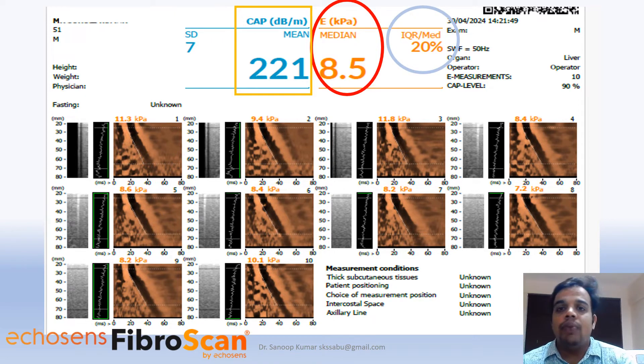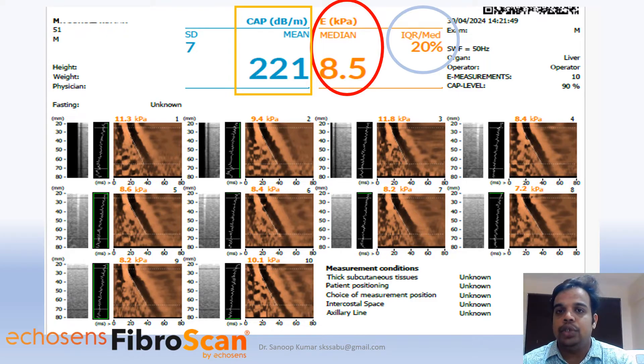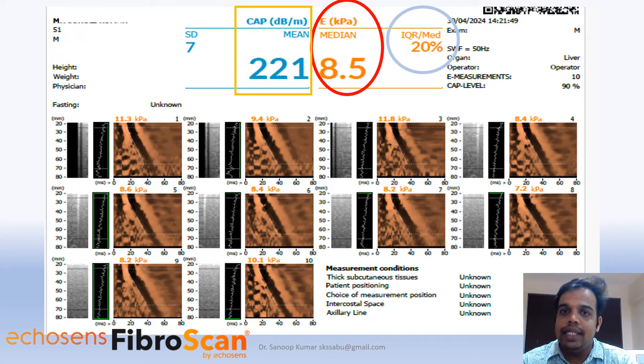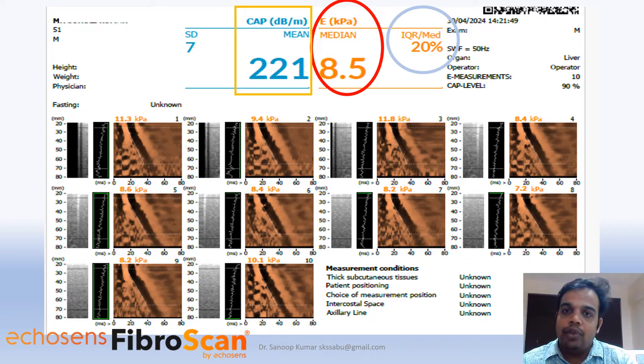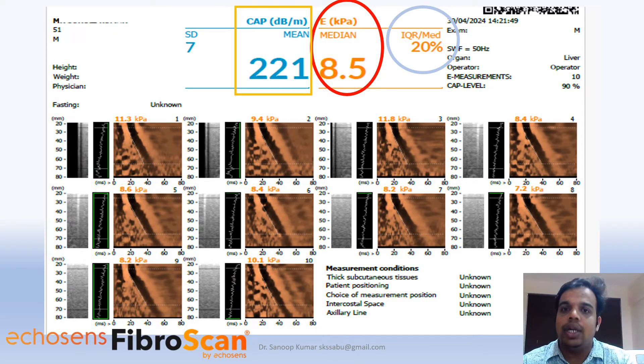Another important value in a Fibroscan report is the IQR per median ratio. This has nothing to do with the patient directly — it is a statistical quality indicator generated by the machine itself, telling you whether the 10 readings can be statistically accepted. Just remember: if the IQR per median is more than 30% or more than 0.3, the test is not valid and will need to be repeated.